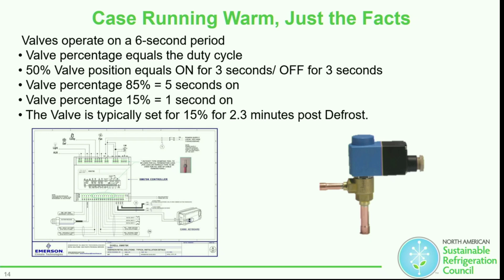Valves operate on a 6-second pulse. Valve percentages equal the duty cycle. 50% valve position equals 3 seconds on and 3 seconds off. That doesn't mean that if it's on for 100%, it's going to be 6 seconds on and then another 6 seconds off. No, it's just going to stay on if the superheat is elevated above its set point. Valve percentage of 85% equals 5 seconds. I'm glad Rusty fixed that because apparently I couldn't math earlier. Valve percentage of 15% equals 1 second on.